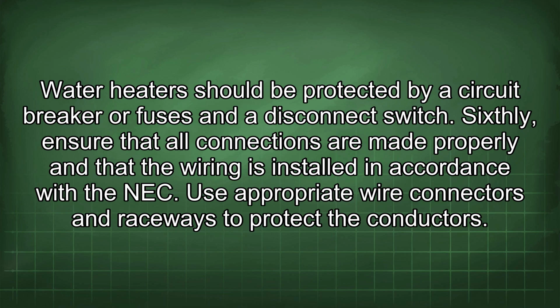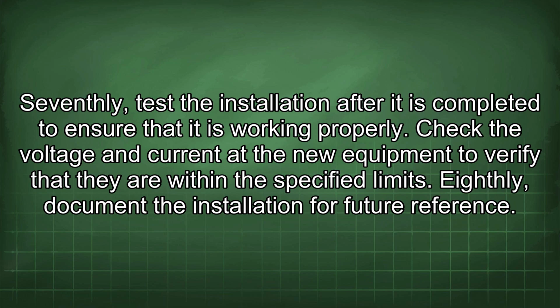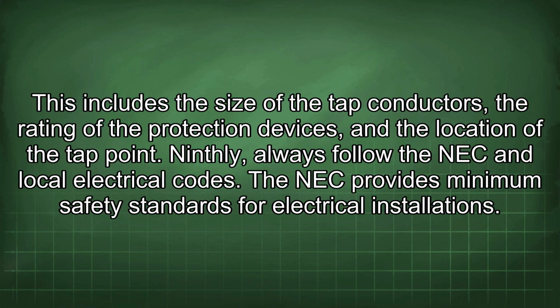Sixthly, ensure that all connections are made properly and that the wiring is installed in accordance with the NEC. Use appropriate wire connectors and raceways to protect the conductors. Seventhly, test the installation after it is completed to ensure that it is working properly. Check the voltage and current at the new equipment to verify that they are within the specified limits. Eighthly, document the installation for future reference. This includes the size of the tap conductors, the rating of the protection devices, and the location of the tap point.